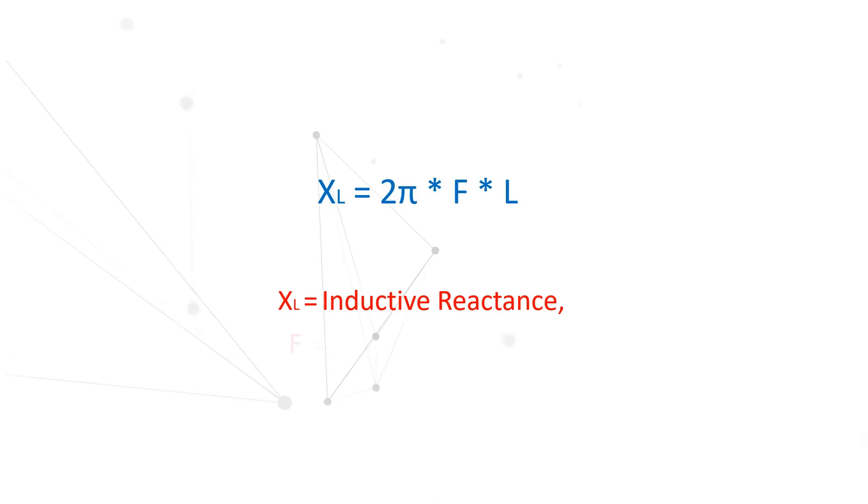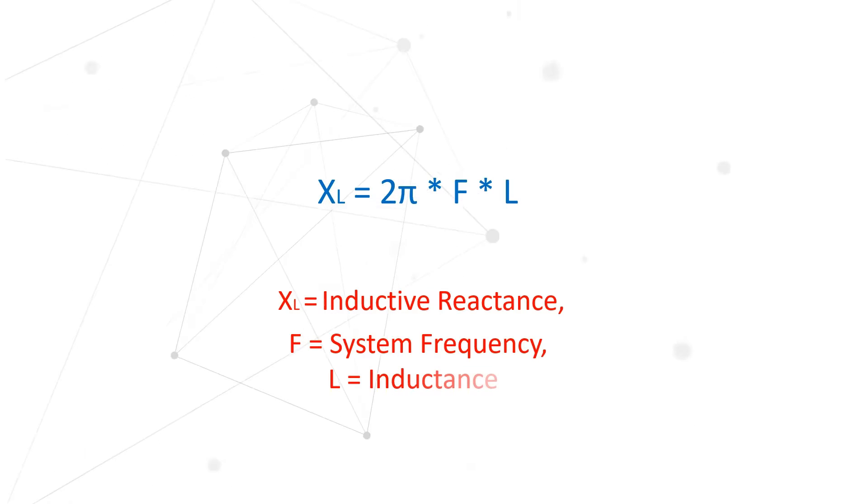As frequency increases, the inductive reactance of the coil rises. This creates high impedance for high frequency signals and low impedance for low frequency signals, effectively blocking the high frequency carrier signal from entering power circuits.